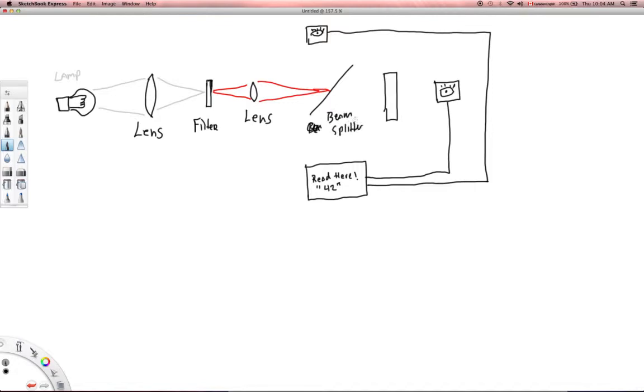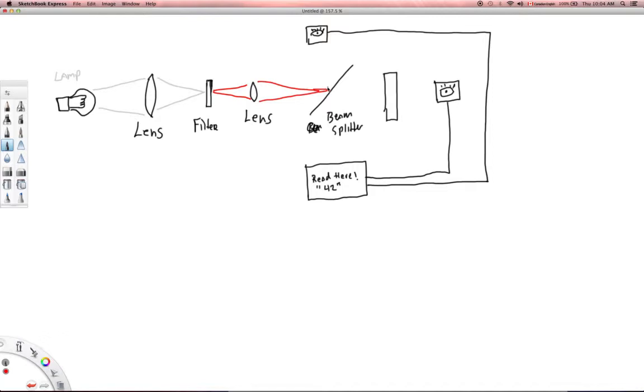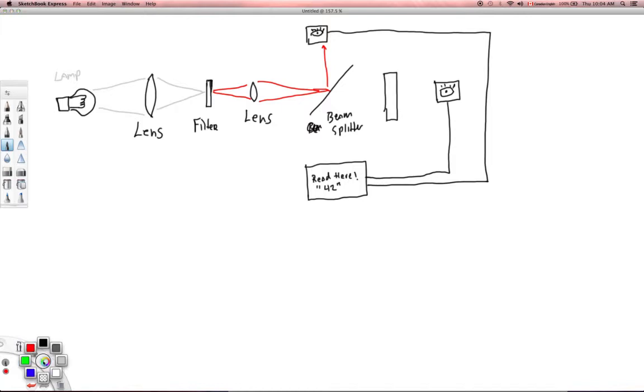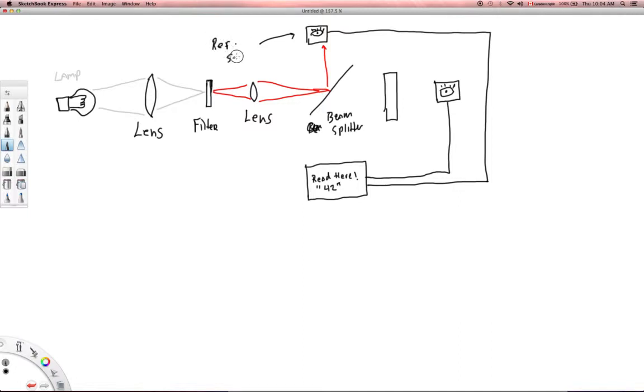And this little thing here is called a beam splitter. All right, and so what's going to happen is part of the beam is going to go up in this direction here. So the beam, this beam of a very specific wavelength of light is going to be split, and some of it's going to go up here. And this is a little eyeball in there that just means a sensor, a detector, and this little thing up here is called the reference sensor.